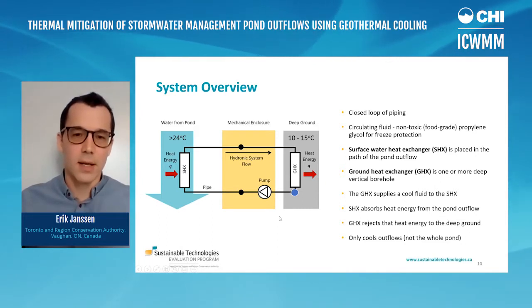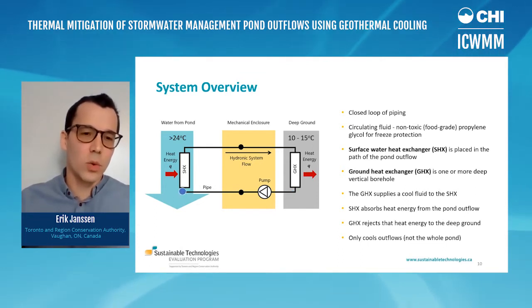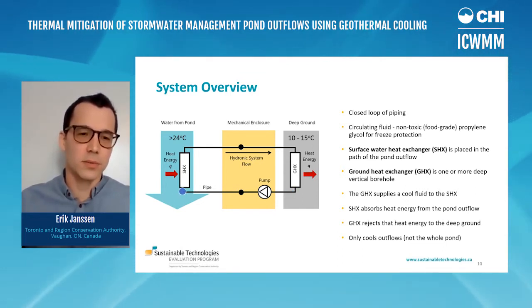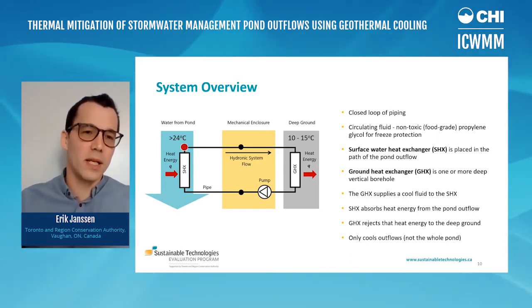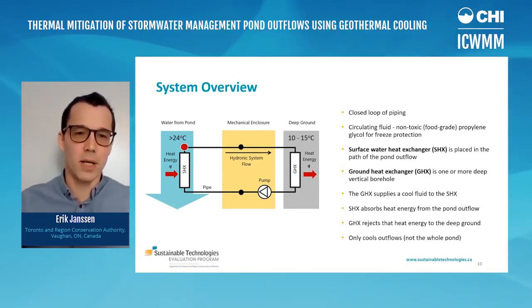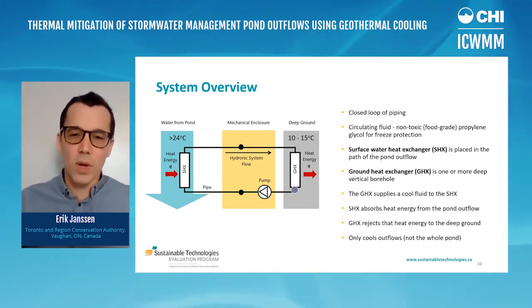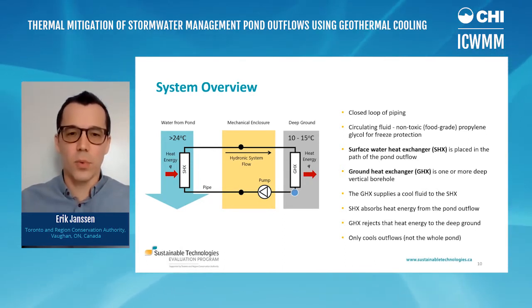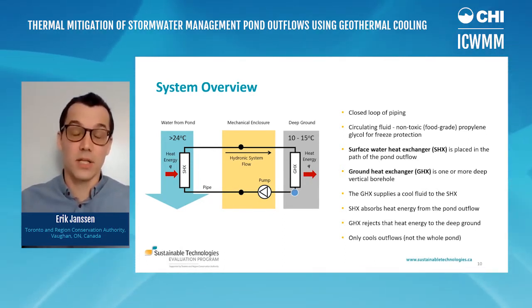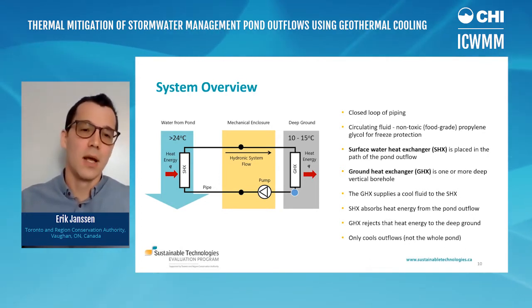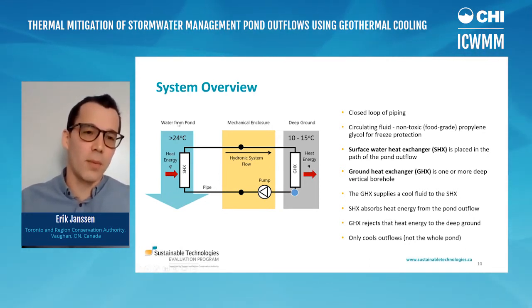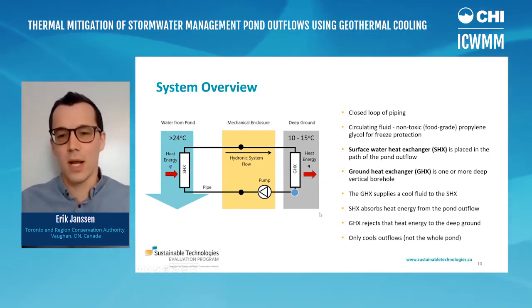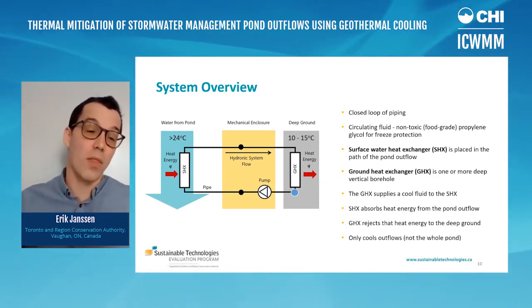So let's just have a look at that. The fluid is represented as the blue circle here. We have a relatively cool fluid being supplied by the ground heat exchanger. It's absorbing the heat energy from the warm stormwater, cooling the water and heating up the heat transfer fluid in the pipe. That's being pumped back to the ground heat exchanger. The heat transfer fluid goes all the way down those boreholes and all the way up again, and the fluid is cooled back to its original temperature again. So in this way, we're absorbing heat energy from the water from the pond and rejecting it to the cooler deep ground. And again, we're only cooling the pond outflows and not the whole pond.